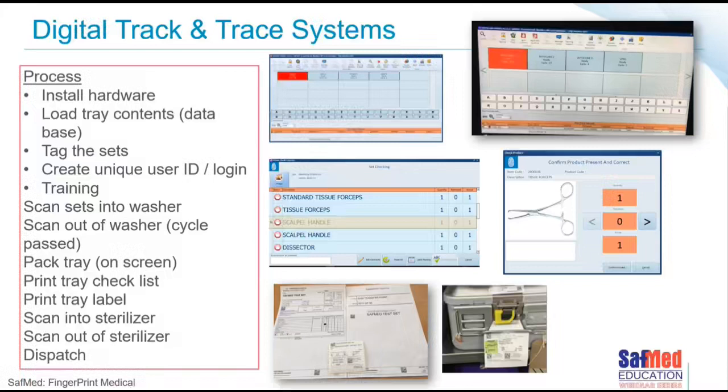I take my tray to the sterilizer, or the autoclave in this case perhaps. I load the rack, put all of the items in. I scan myself, log on to the system. It's sterilizer number 2 that we are using today. I acknowledge that this is going to sterilizer 2, and then I scan all the items. I still need a process challenge device in there. That is still something that is of importance. I'm still using that. That doesn't go away.